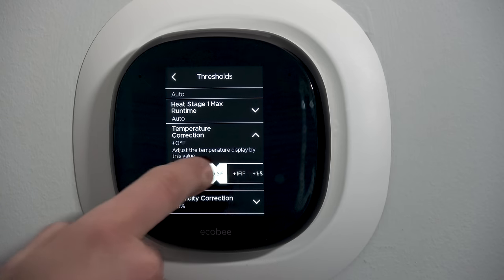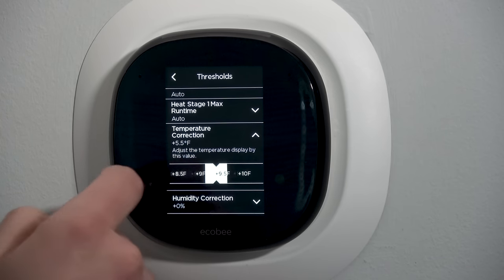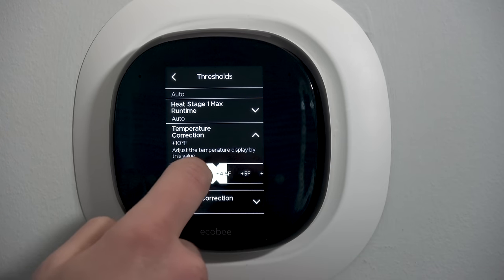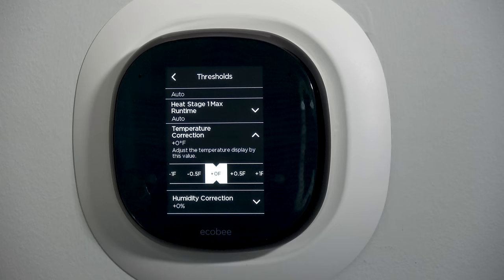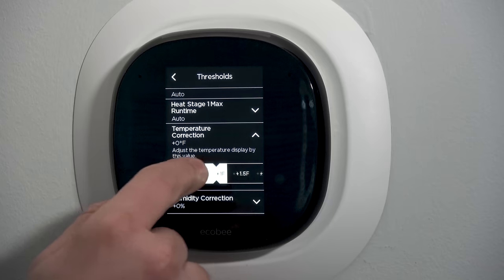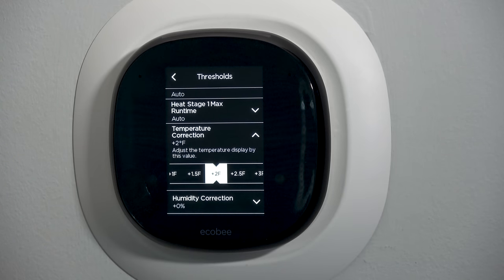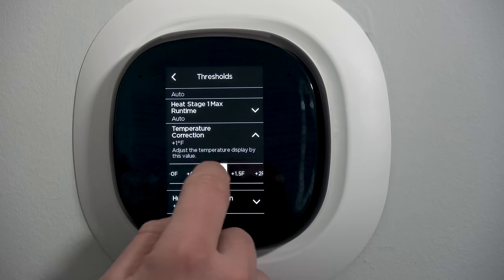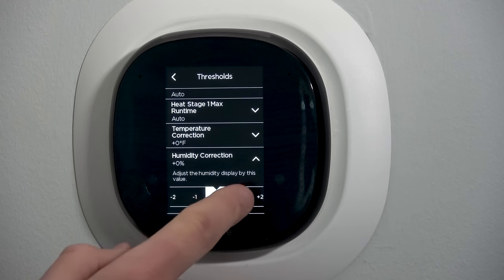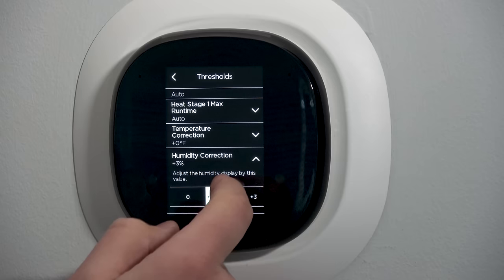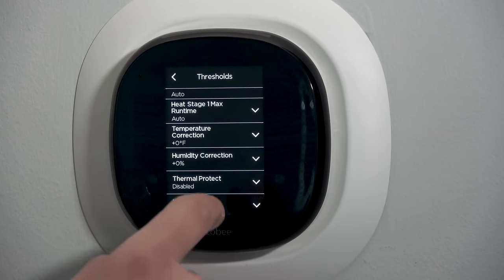Temperature correction: I can add plus or minus 10 degrees in half-degree increments. These are pretty accurate sensors, but if a customer says the stat reads 72 and they believe it's really 74, you can come in and add a two-degree offset so it reads and controls to 74 — calibrating the sensor to match their other device. Same thing for humidity correction: plus or minus 10 percent in one-percent increments to calibrate the humidity reading to match whatever other device the customer has.